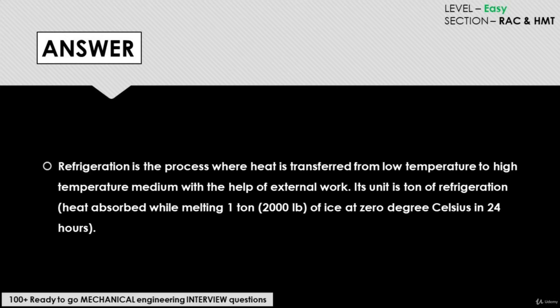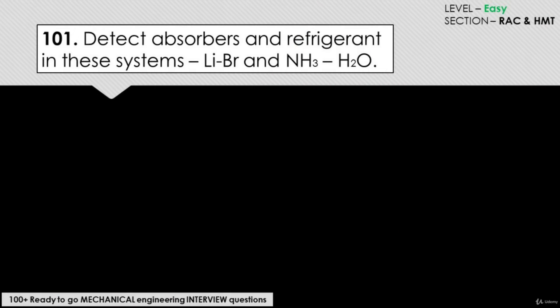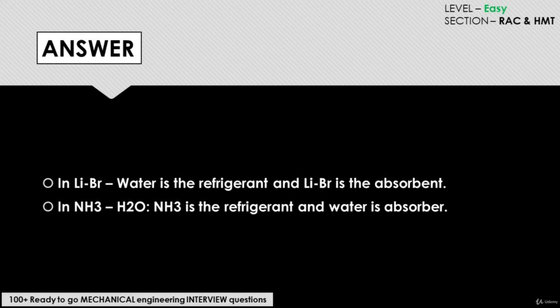The unit of refrigeration is the ton of refrigeration — that is the heat absorbed while melting one ton of ice at zero degrees Celsius in 24 hours. In the system shown, LiBr-H₂O uses water as the refrigerant and lithium bromide as the absorbent. In NH₃-H₂O, NH₃ is the refrigerant and water is the absorber.